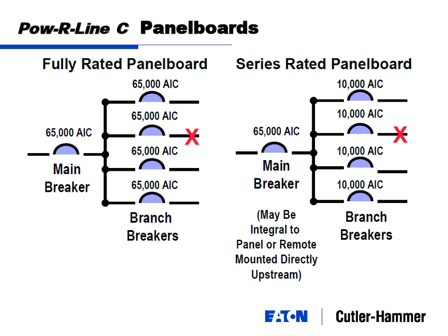So what that means is, you've got a fully rated panelboard, a 65,000 amp main breaker, and all your feeder breakers are rated 65,000 amps. If a fault occurs on the load side, your current can flow through any of these breakers, and any of these breakers can trip and take the fault offline. In a series rated panelboard, I still have my 65,000 amp rated main breaker, but I'm using 10,000 amp rated feeder breakers as branch breakers. And what our UL testing tells us is that if a fault occurs in the same location, it still has the ability to take this fault offline, no matter whether it's the 10,000 amp breaker or the 65,000 amp main that is tripping.